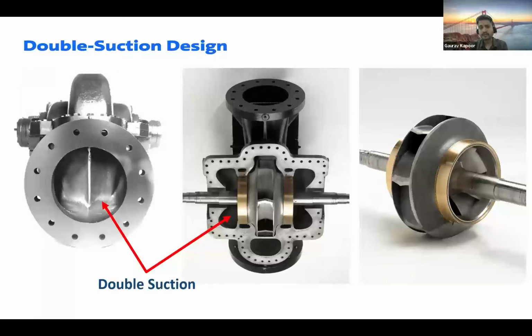We call it double suction design. Why double suction? So this is the suction side of the pump, and if you see, this has a ship type hull structure. So when such a large amount of water is being pushed through the pump, it is equally divided in two ways and enters the pump casing from two sides into the impeller. If you see, this is a double eye impeller. It is like two impellers welded back to back, but it's a casted impeller.